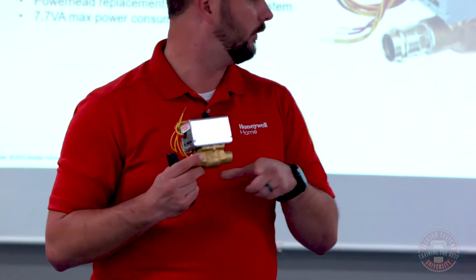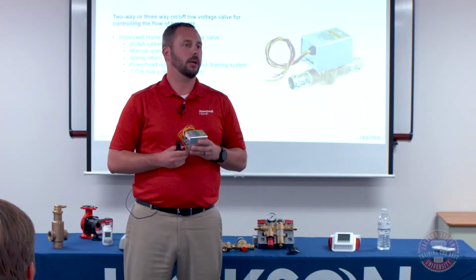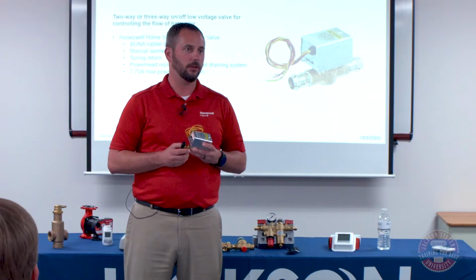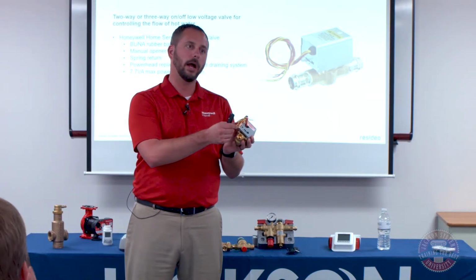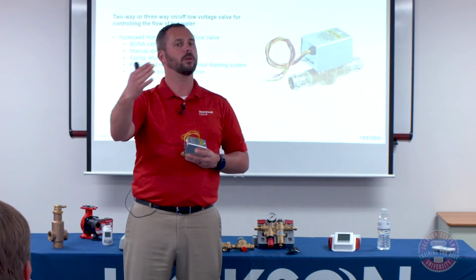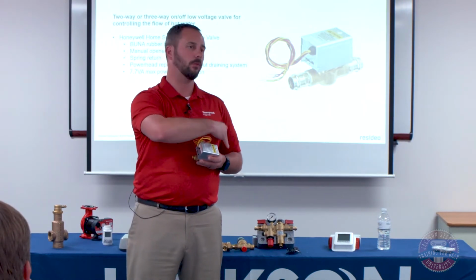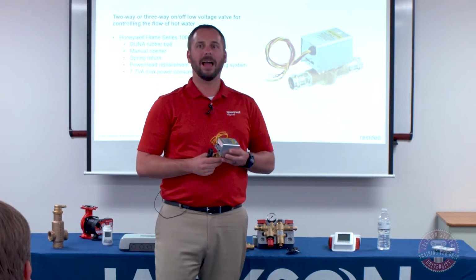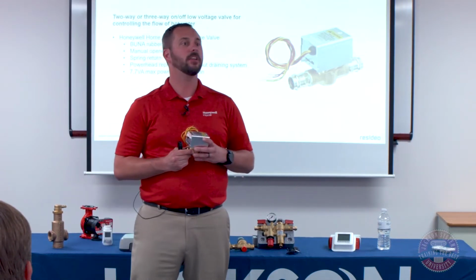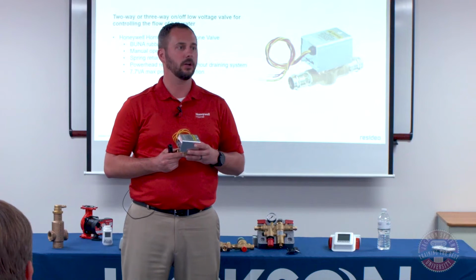We do make a series of valves, which I unfortunately do not have in this presentation, that you can open and close without having to keep it energized. It's a 3-wire style, whereas this one only needs 2 wires to open. That series of valve needs 3, because you have to give it 24 volts to open it, and then 24 volts to close it. So I don't have that in this presentation, but we do have a different series of valve that could handle one that doesn't need constant power.